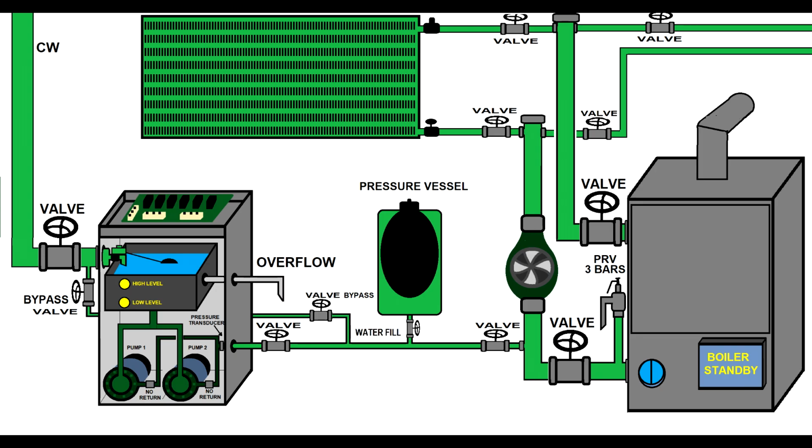what happens. Now we all know that in the beginning the tank is empty. Inside the pressurization unit there's no water in the system. We check all the system. If everything is okay, we check the motors, we check the electrical connection. Technically we check everything to make sure that our installation is safe and sound. Now the first thing to do when we want to fill our installation is to open the valve of the main cold water supply. We open the valve and we have time to check for leaks.